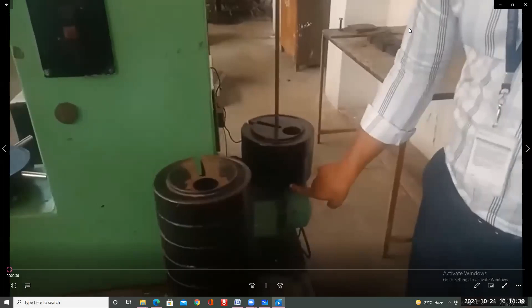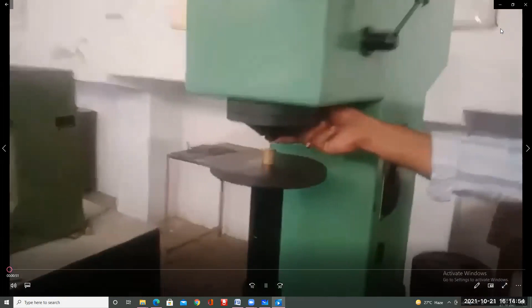Here the applied load is 1000 kg. That means the pan is 250, another 250, that is 500, once again 250, totally 750, and the built-in weight contains 250. Totally the effective 1000 kg is going to be acting onto the indenter. This is the indenter; we are fixing the indenter knob.